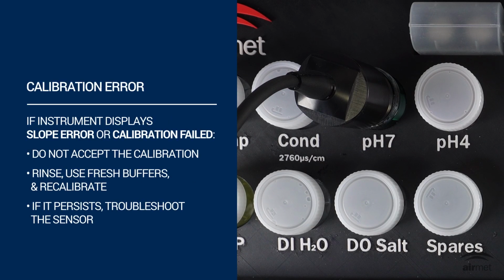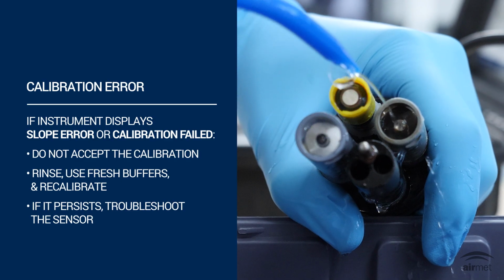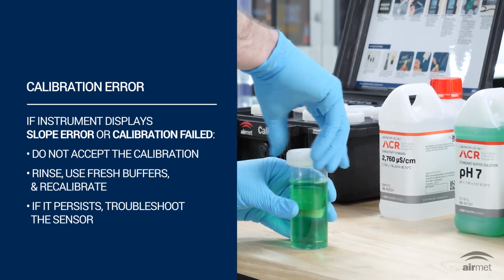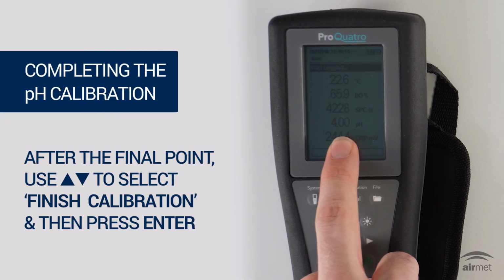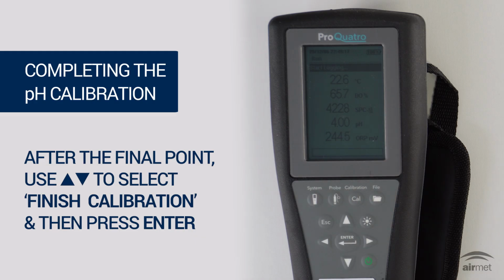If the instrument displays a slope error or calibration failed, do not accept the calibration results. Rinse and use fresh buffer solutions and recalibrate. If the issue persists, troubleshoot the sensor. After the final point, confirm the calibration completion and return to the measurement mode, ensuring the calibration is stored.